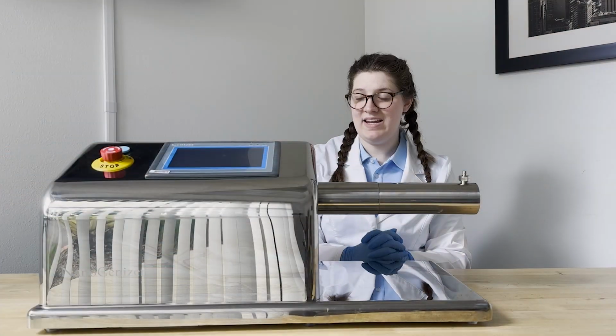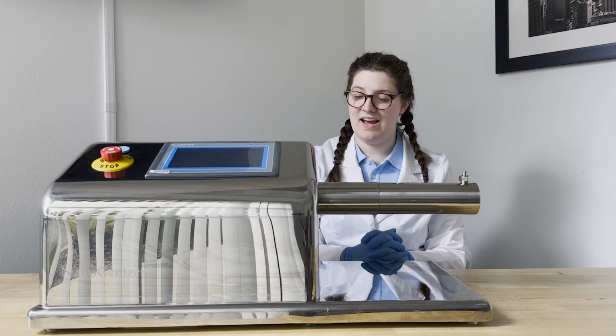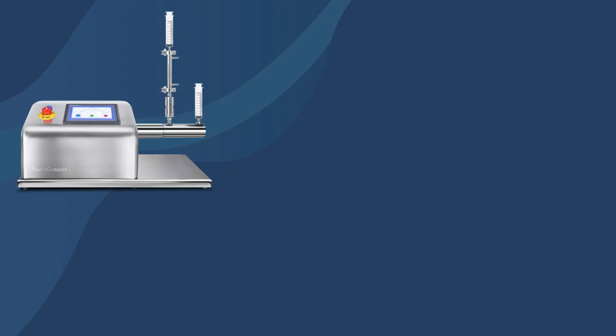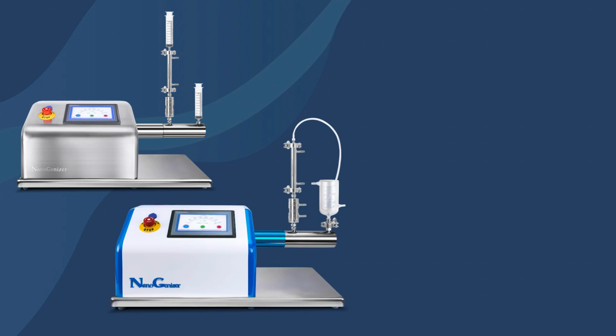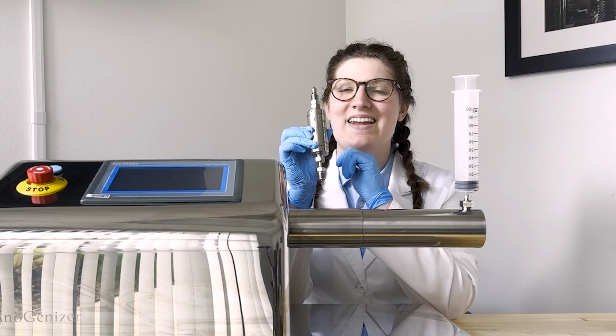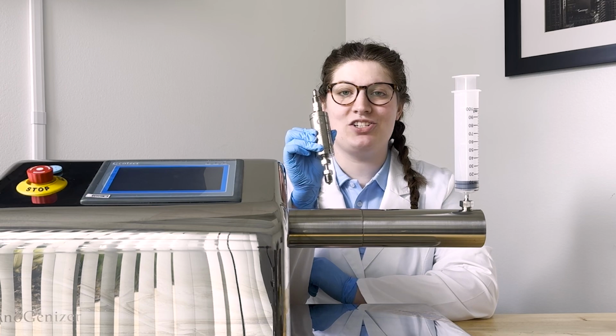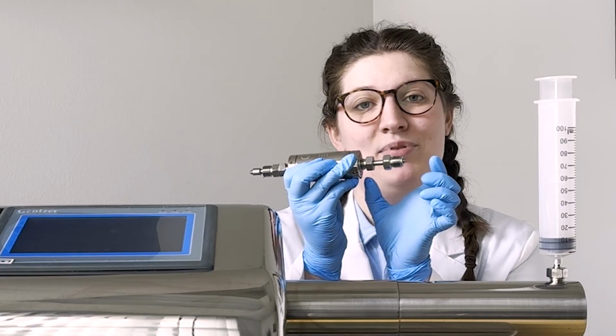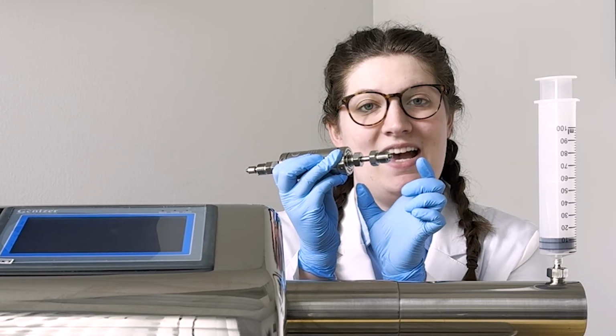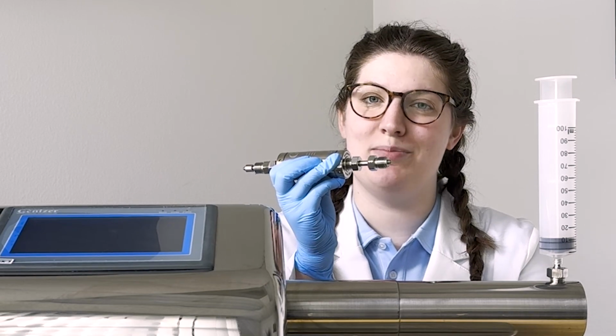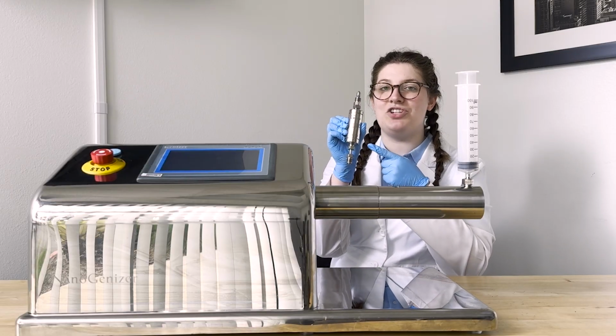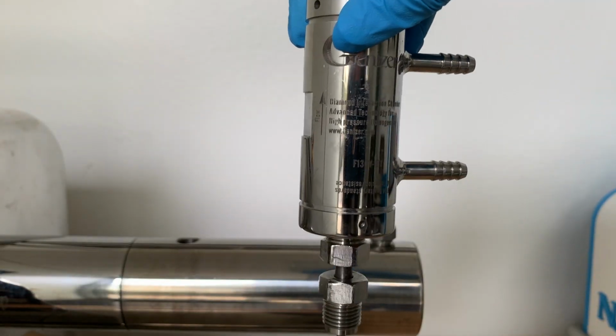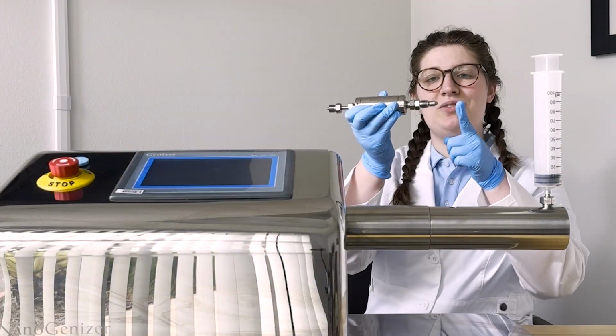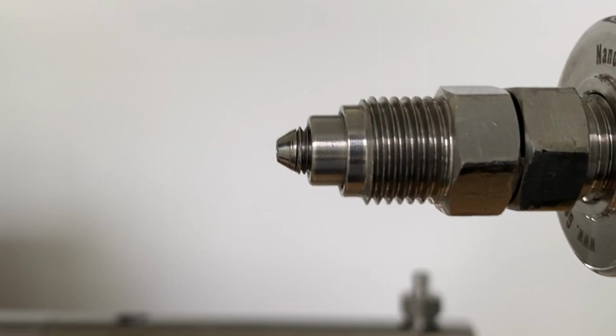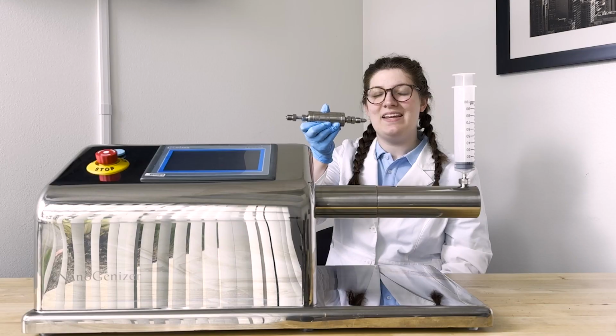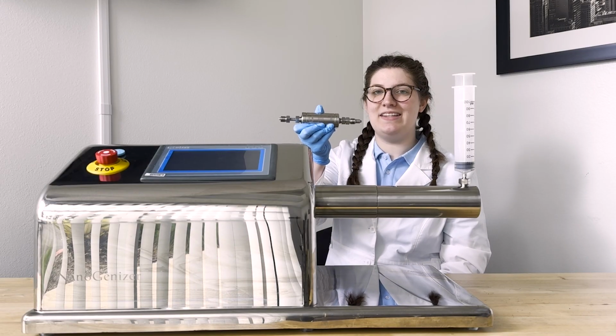There are a variety of inlet options, including an attached tube, a luer lock syringe, and a glass or stainless steel reservoir. Now let's attach our diamond interaction chamber using the high pressure nipple assembly that will come attached to your diamond interaction chamber. You will want to orient your chamber with the writing facing right side up. Leave 2 to 3 threads visible when turning the collar. This step is important for preventing leakage.